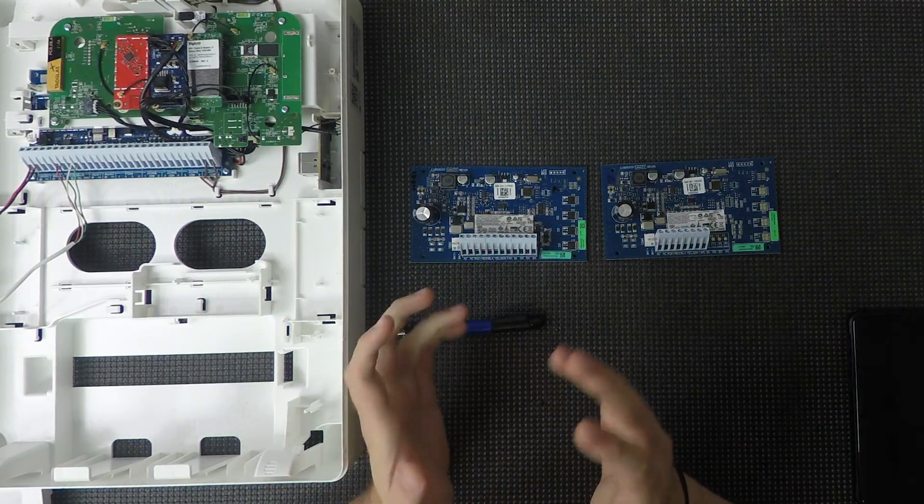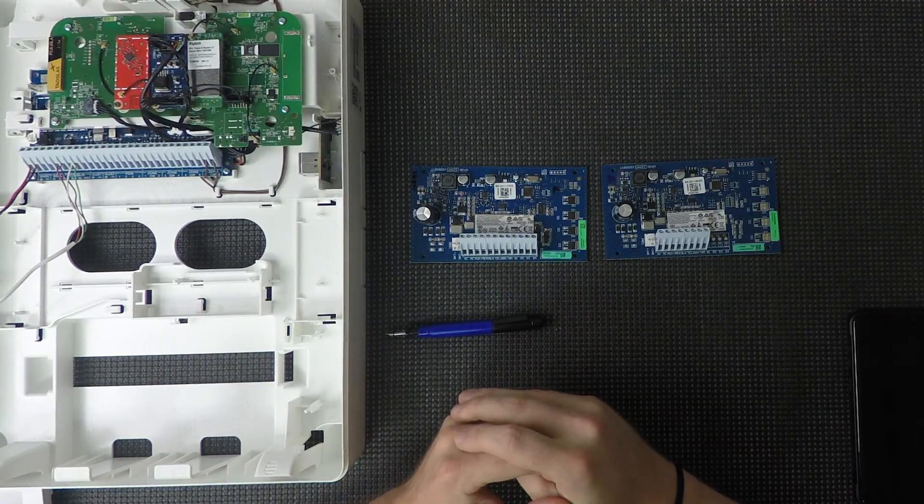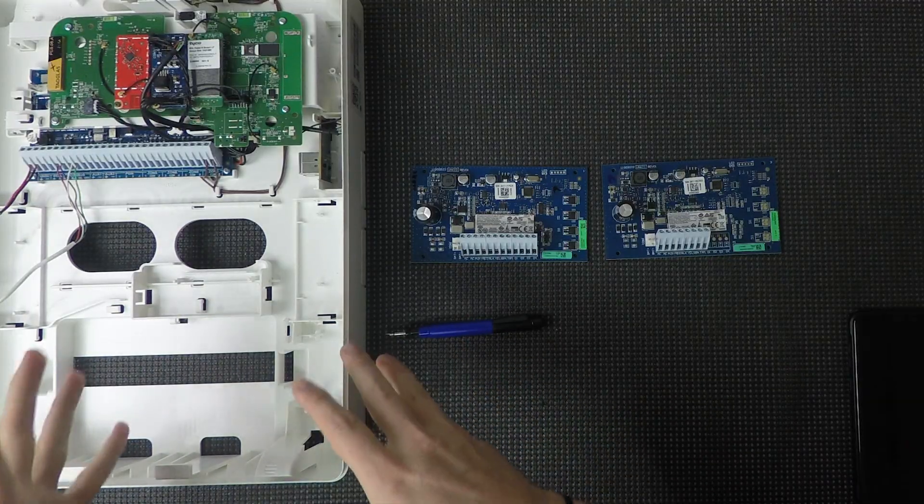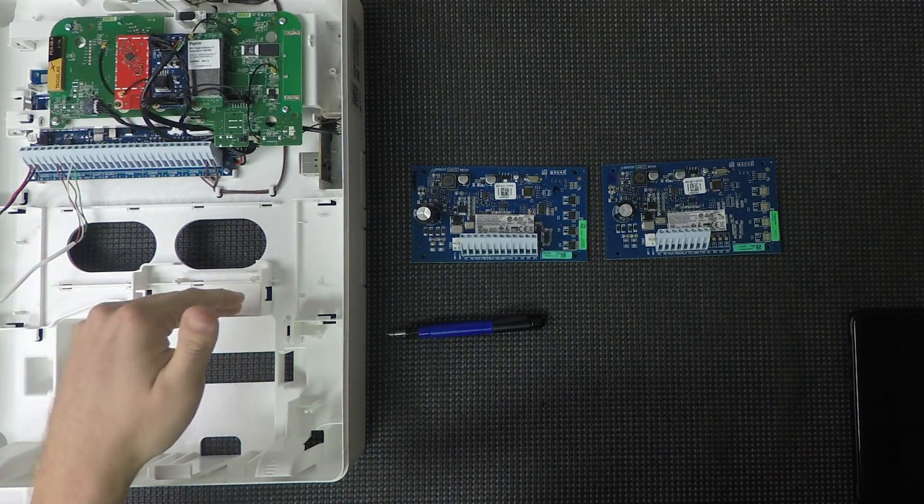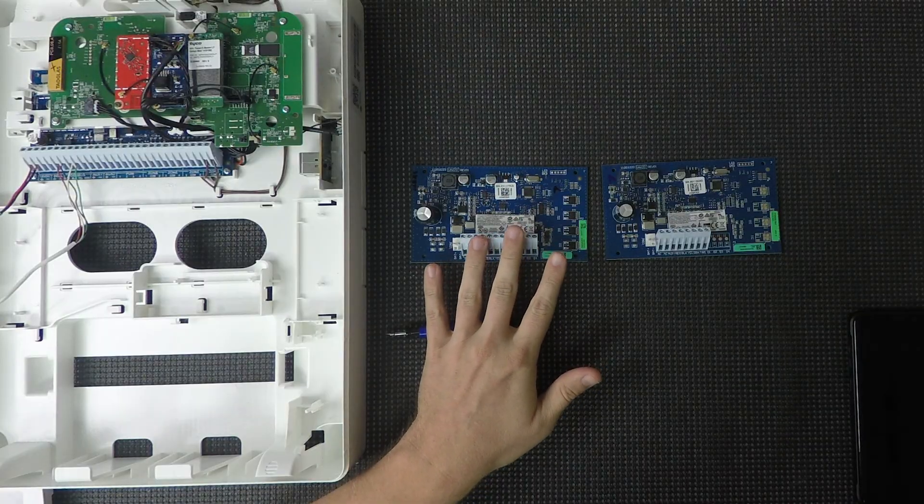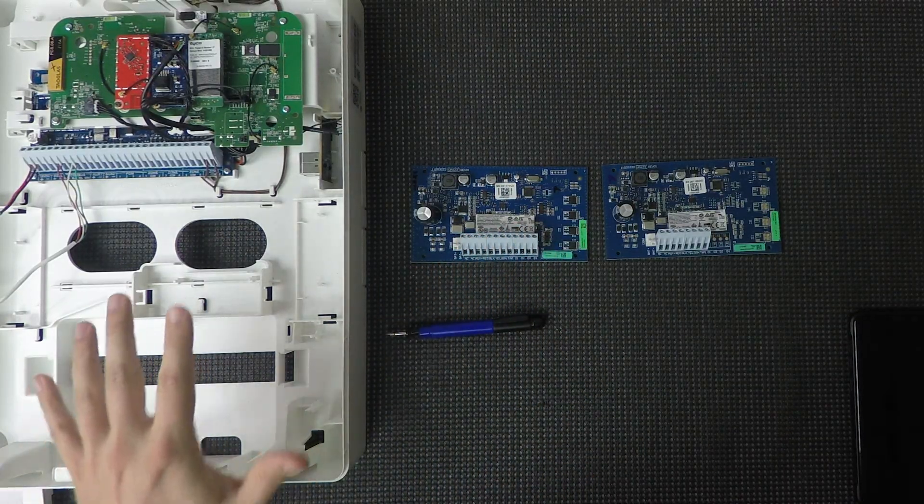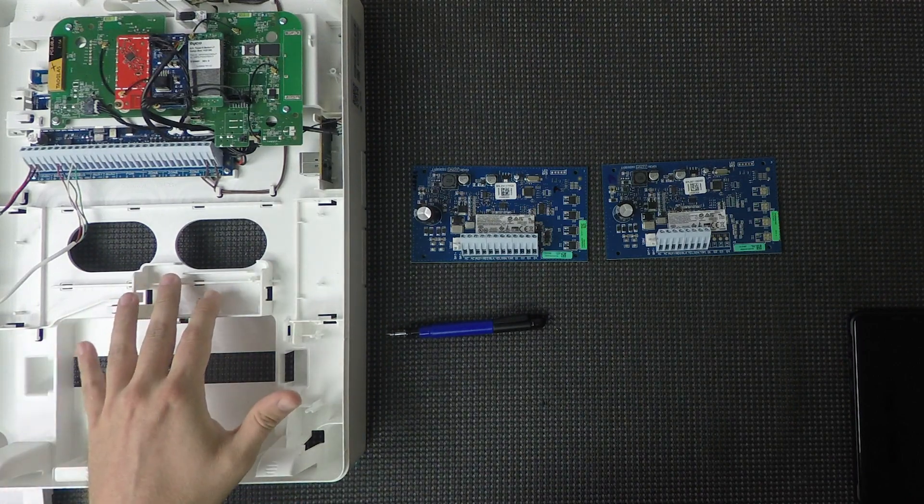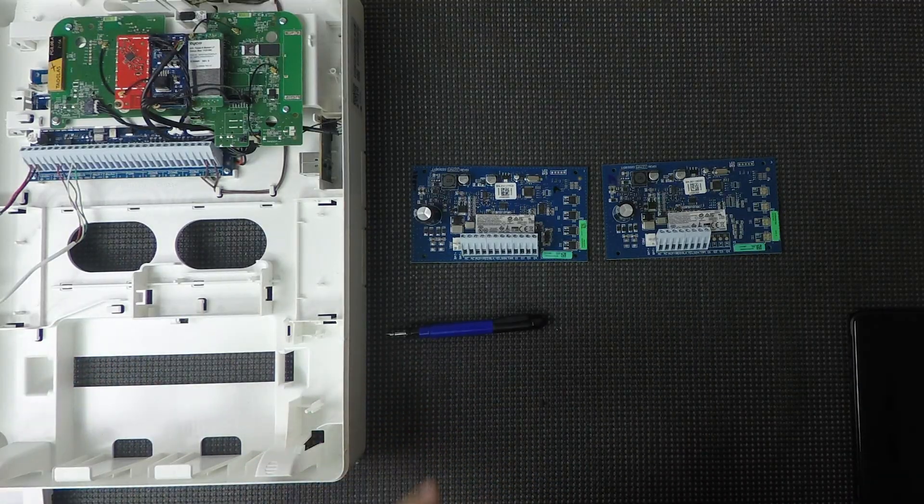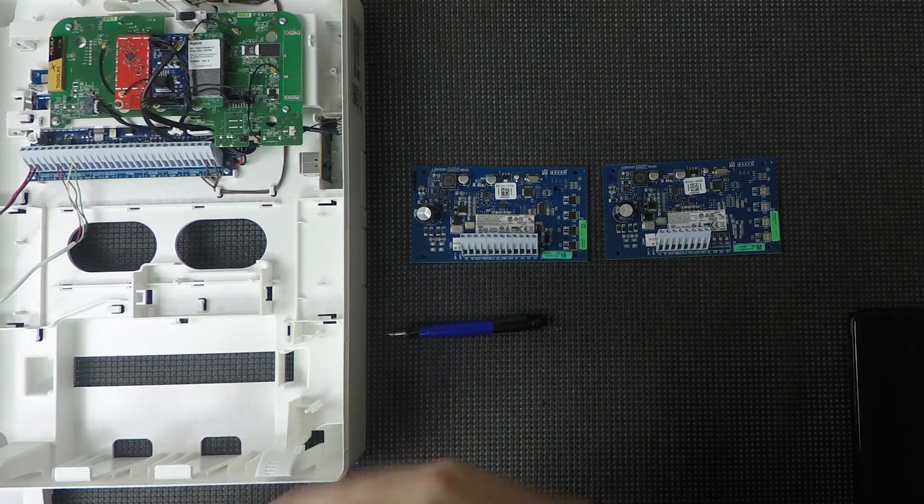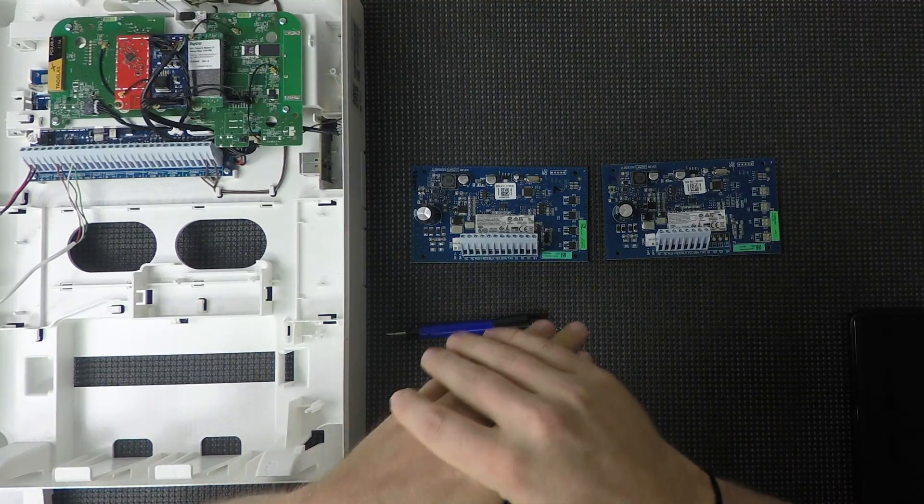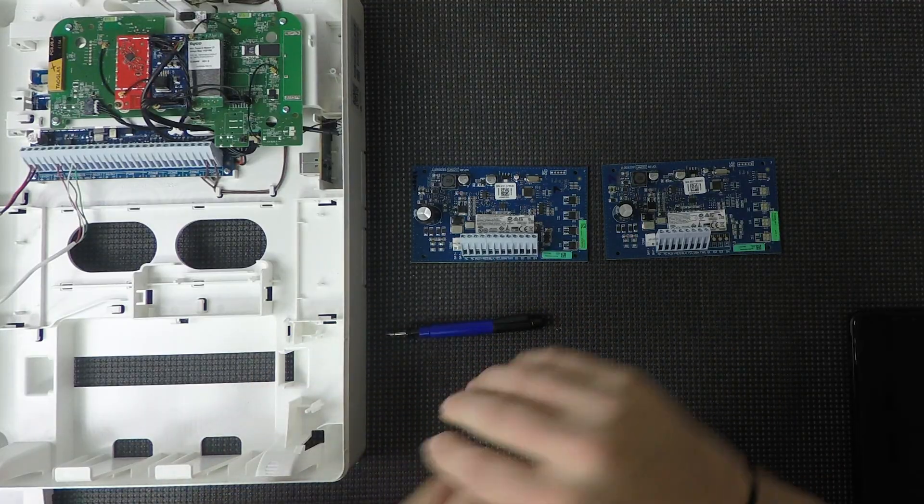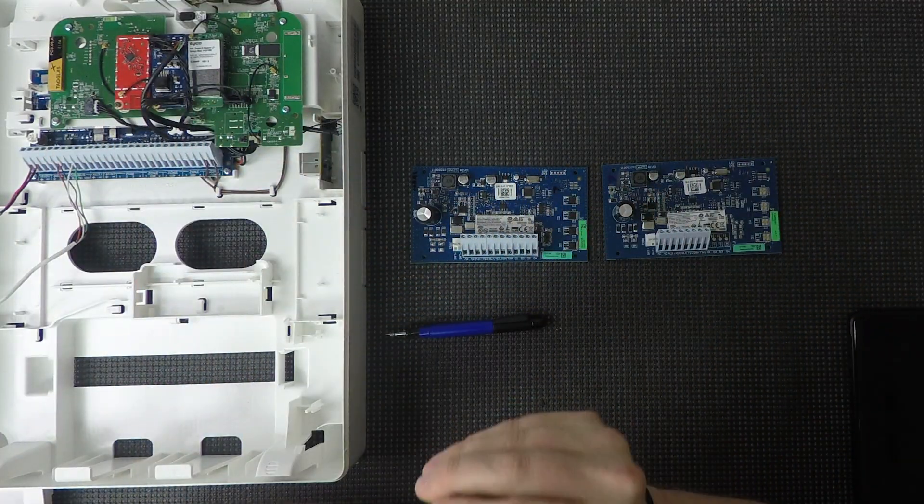On that note, it generally is recommended you use an additional cabinet for a power supply module. Mainly because when you're using the IQ Pro, especially in this plastic cabinet, there is no space for it in here. This has spaces for a few zone expanders, however, there is no space big enough for the power supply. The metal cabinet does technically have enough space in it, however, I don't have one of those handy so I couldn't tell you exactly where it would mount. However, there is the PC-5003C extra cabinet, it's a 12x12 DSC cabinet we carry on our website. You can get one of those, stick that in there. It's already got proper mounting holes, so you're good to go.